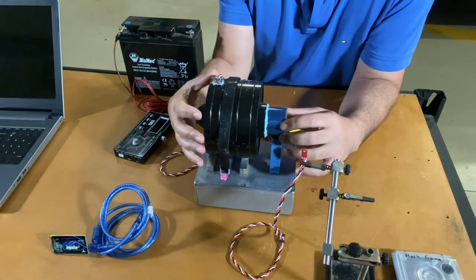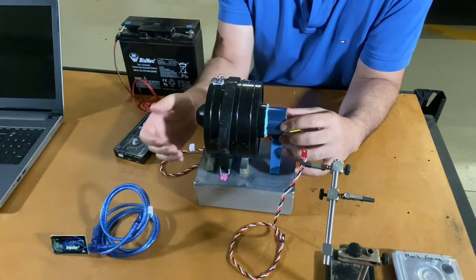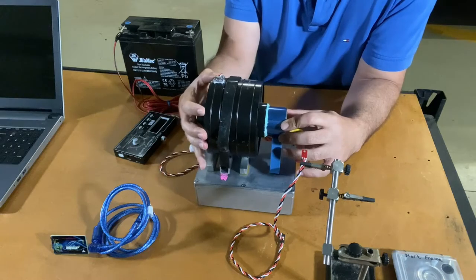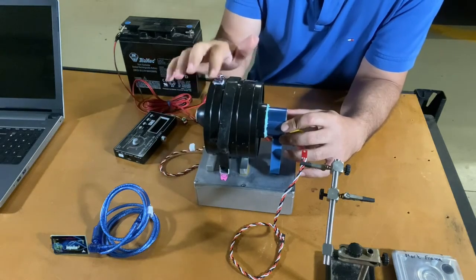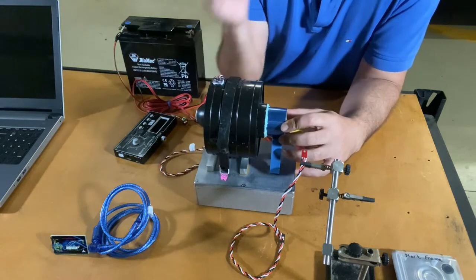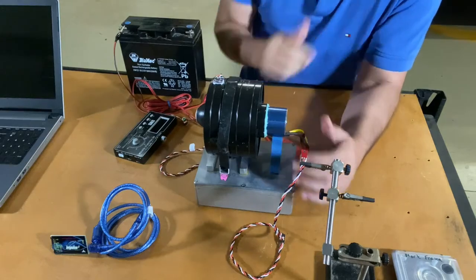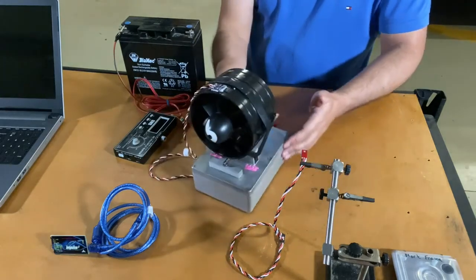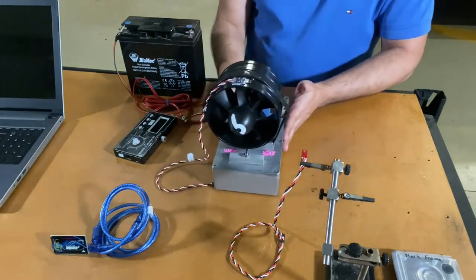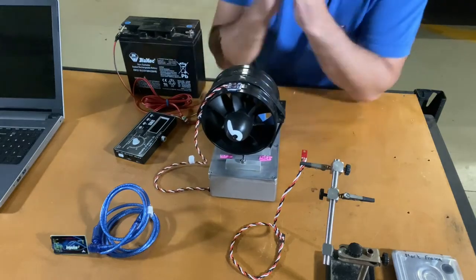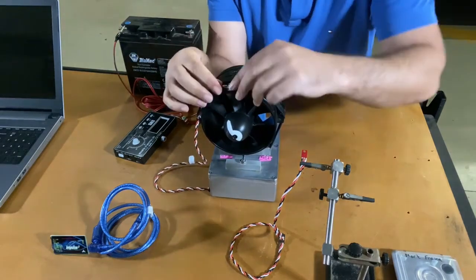So ideally, when the impeller is running at speed, it's oscillating like this, and the sensor, which is located directly above, is sensing that vibration. So I'm just going to rotate around now to show you how the sensor is installed. So the sensor, I'll just take that off.